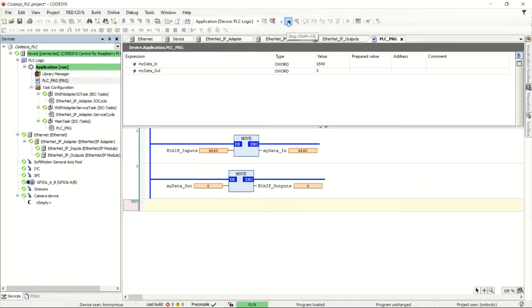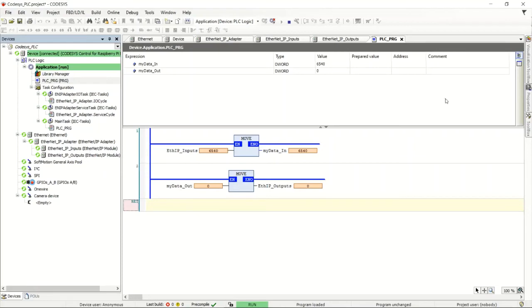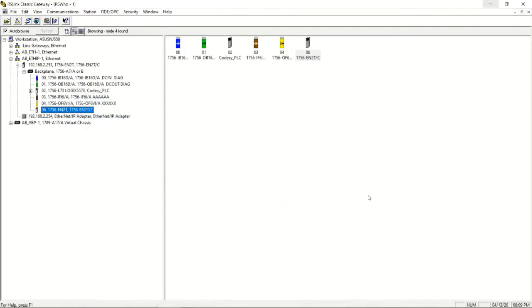When you stop the PLC, the green circles turn gray, meaning it's not scanning. Press play and it starts scanning again. If you have a misconfiguration or communication problem, you'll see triangles — like little yield signs with an exclamation mark — indicating it can't talk to the PLC.